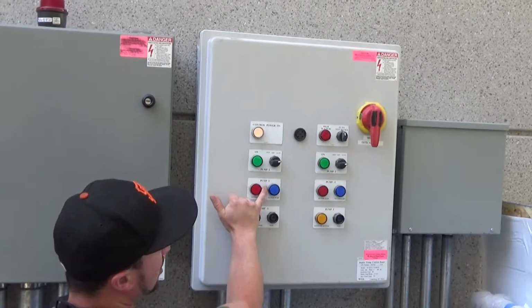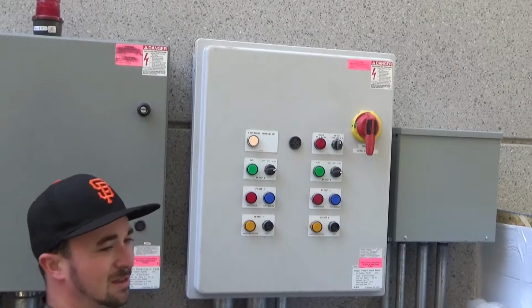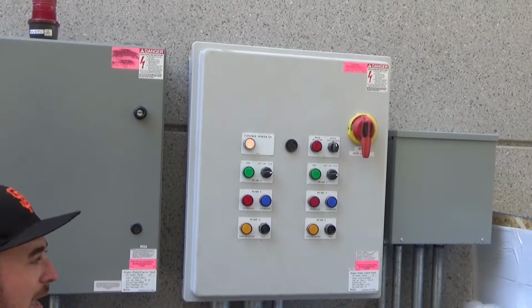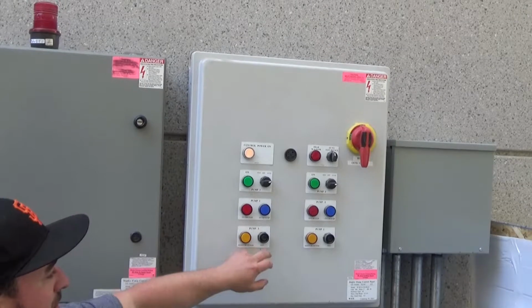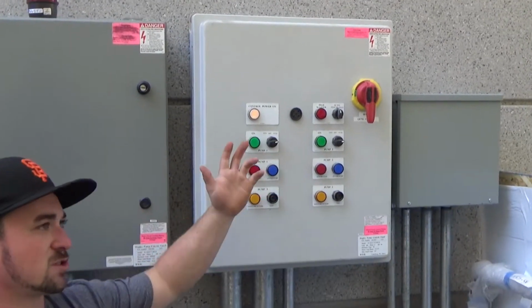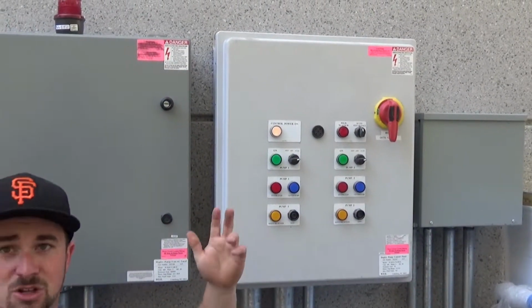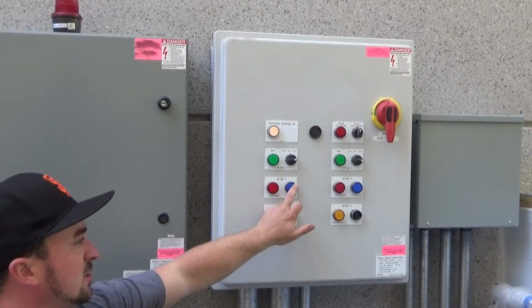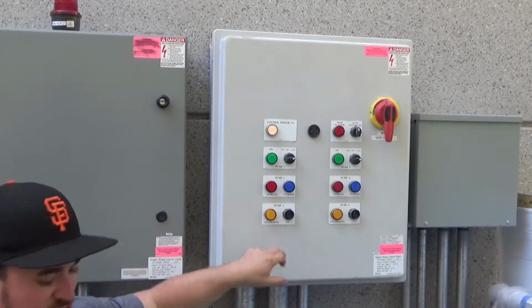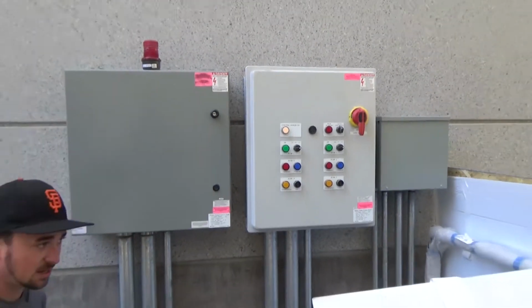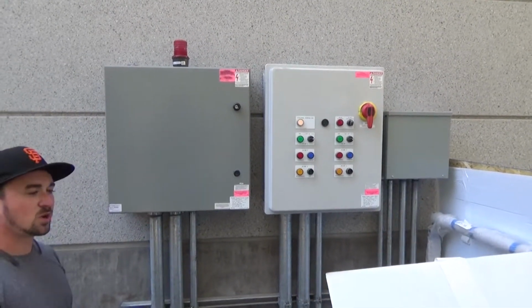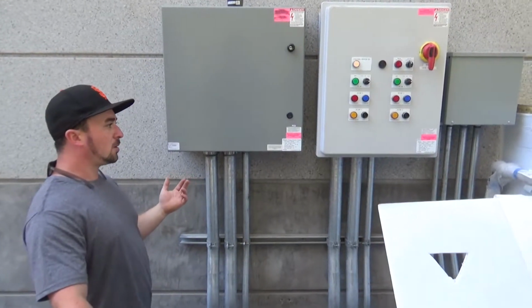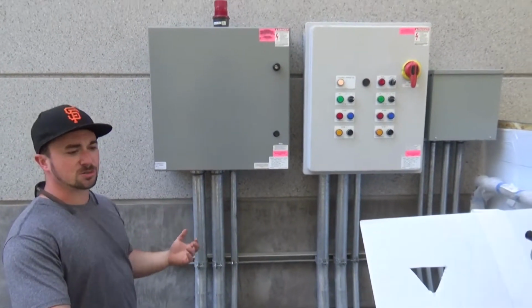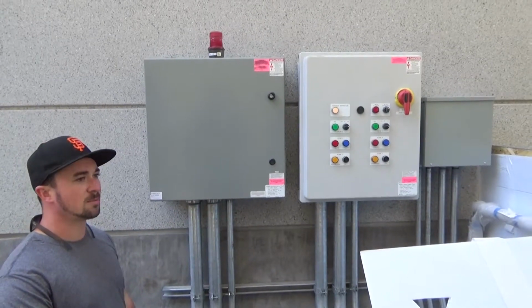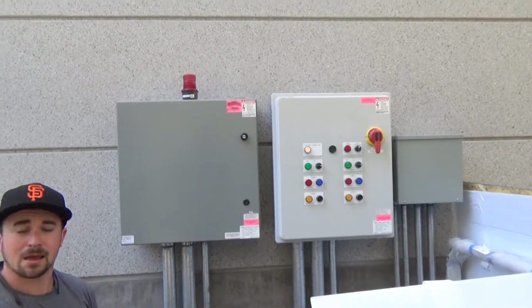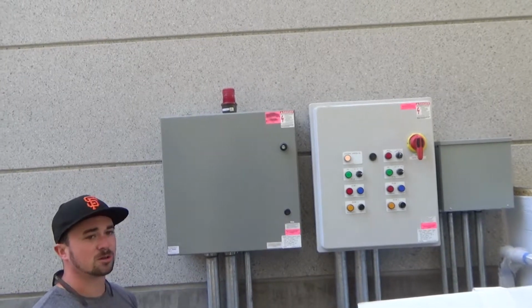So this is for overload, so that's over amperage. Something got stuck in the pump or something happened, the pump's drawing too many amps, that'll be lit up. That's for your over temperature, so somehow the water gets too hot, the pump's deadheading, not shutting off, heating up, it protects the seal, that thing goes off. Moisture sensor: the moisture sensor is located on the inside of the pump, where the seal is located. If water gets past that internal seal that protects the motor, that moisture sensor is going to trip, and it's going to keep that pump from turning on. Another one of the safeties, just to make sure you don't completely ruin that motor.